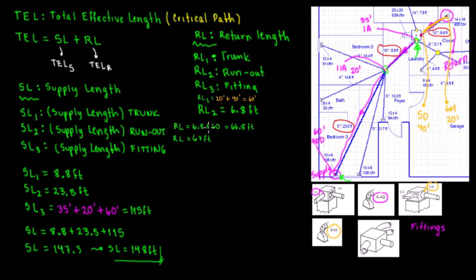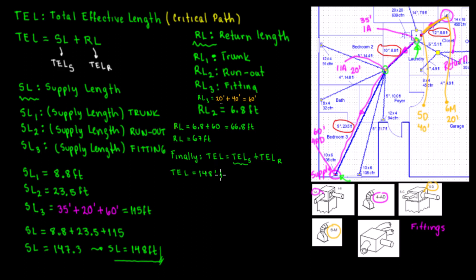Now that we have both lengths, the TEL — Total Effective Length — is equal to TEL of the supply side plus TEL of the return side. The supply side was 148 feet plus the return side was 67 feet, giving us a total TEL of 215 feet.